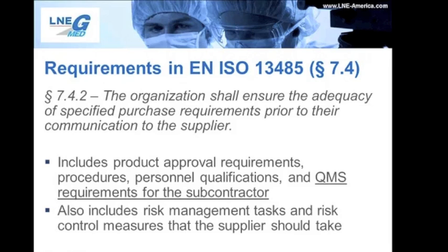Now, this includes product approval requirements. For example, if a person with specific qualifications is required to build a device, and procedures the subcontractor itself should have in place before starting. In some cases, like when a distributor is a critical subcontractor, the manufacturer also must make sure that the subcontractor performs its risk management tasks according to the manufacturer's requirements and specifications.